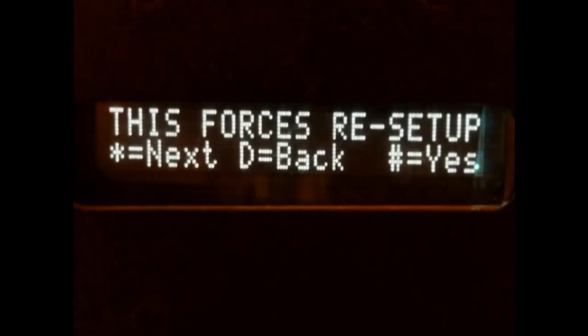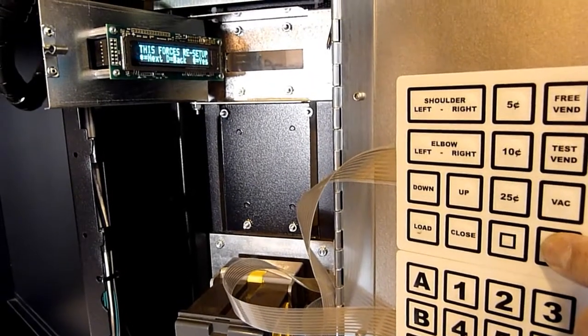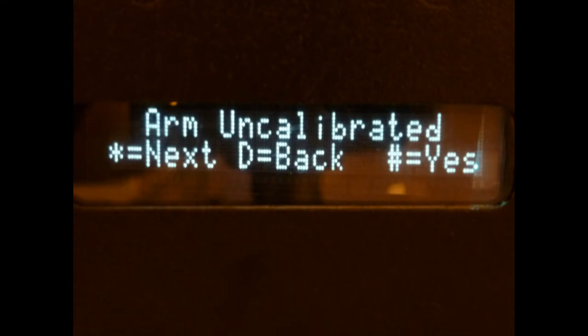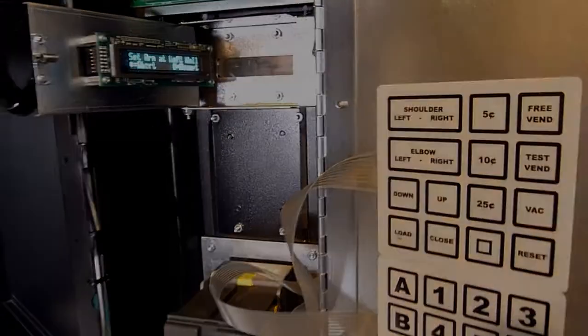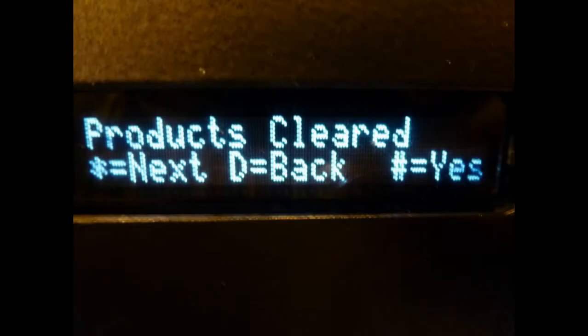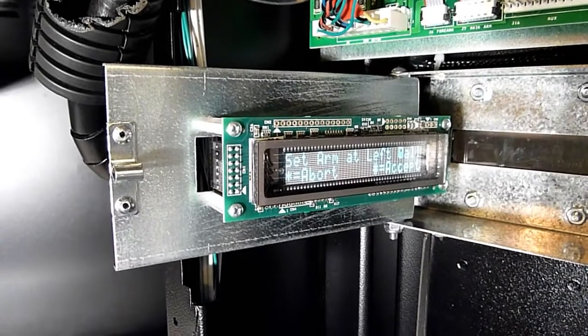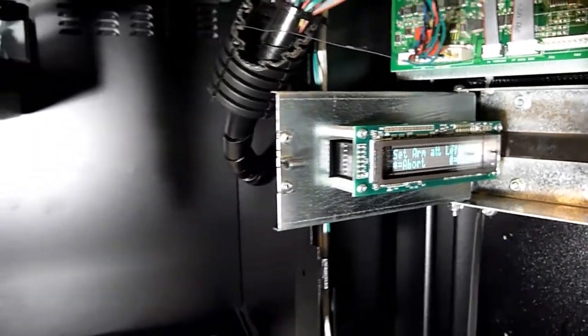The display will first read, "This forces resetup," and when the display changes to "Arm uncalibrated," immediately release the reset button. If you continue to hold the reset button past this point, the display will change to "Products cleared," and you will have erased all product selections and programming. Press the pound key to continue.